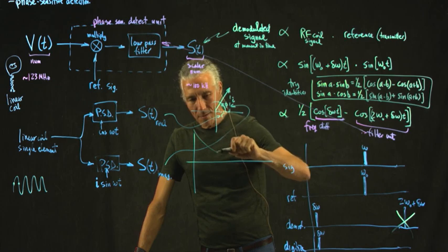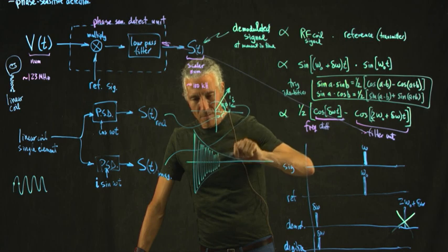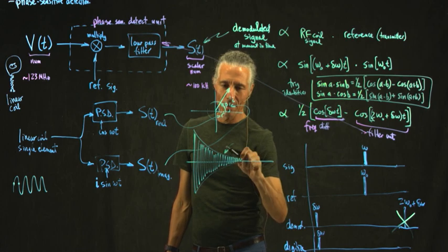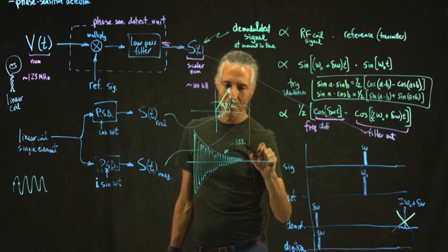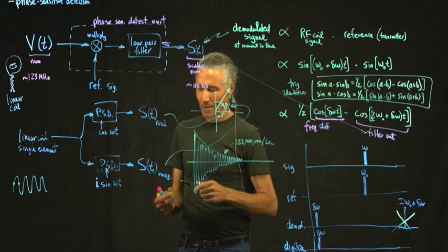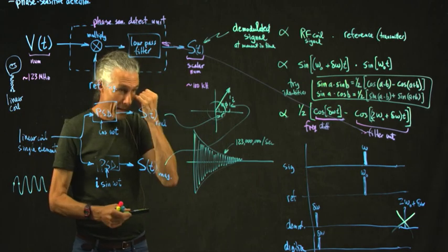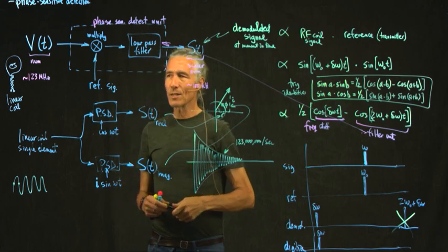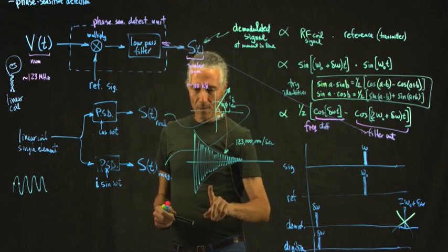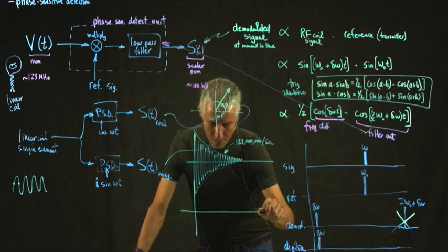Well, it's going to have this exponential decay, and it's going to be cycling up and down like a very rapid sine wave, but I haven't drawn anywhere close to the number of wiggles required. So this is 123 million per second. That's the actual signal that comes out of the terminals of the coil. And after we've done the phase-sensitive detection to it, we get a much lower frequency signal. So what does that lower frequency signal look like? Well, it's got two parts.